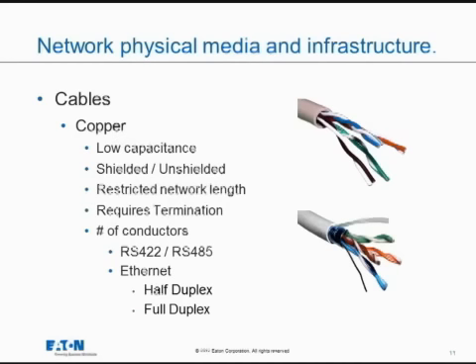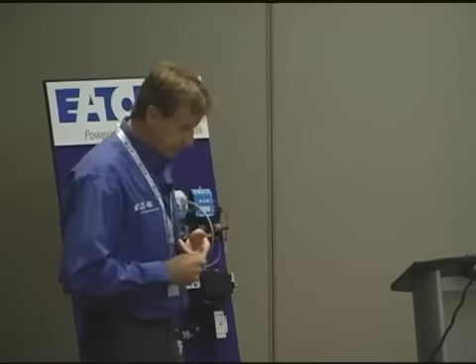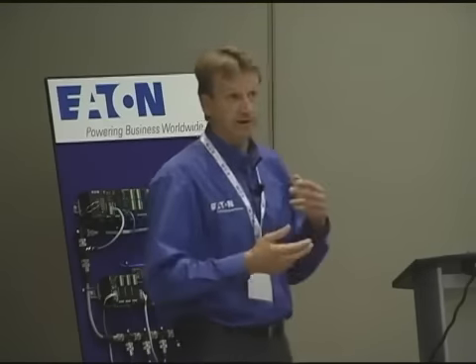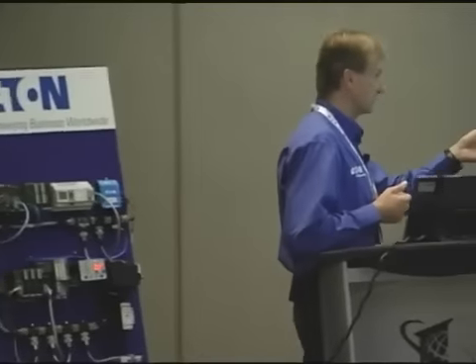Number of conductors is another consideration. Serial protocols like RS-232, RS-422, RS-485 dictate how many conductors you need. For Ethernet, there are specifications for how many pairs to use. This ties into half duplex versus full duplex: in a half duplex system you cannot transmit and receive at the same time — you transmit and then wait to receive. Full duplex means you have two sets of data lines — a transmit line and a receive line — so you can do both simultaneously, resulting in much faster communication speeds.